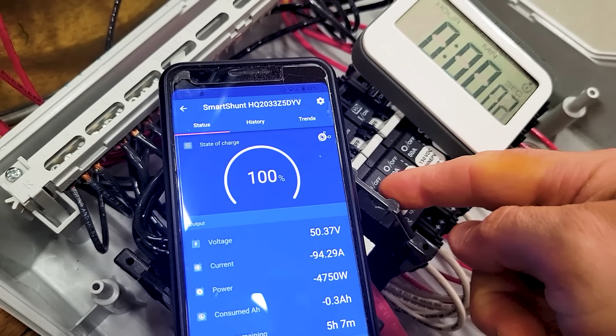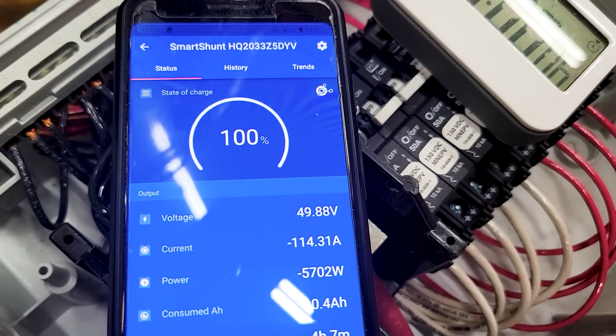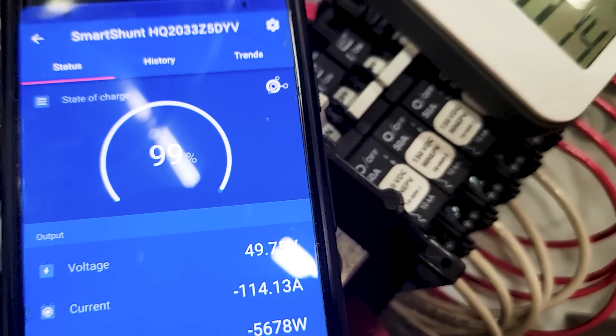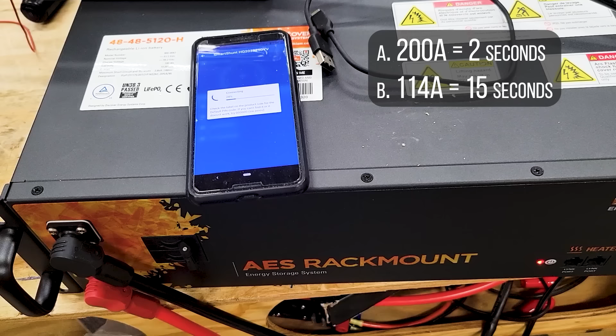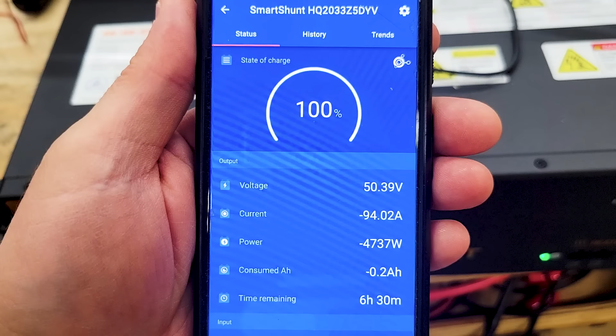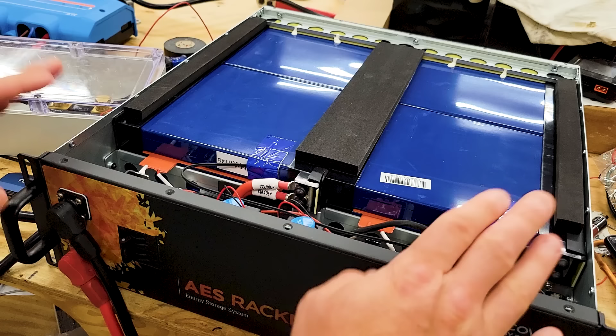Okay, so now we have 95 amps. Let's turn this on. And let's try turning on just one additional circuit breaker. So now we're at 114 amps, and now it died after about 15 seconds. So now we can see we have a red light flashing, the circuit breaker is still on, so now there should be a 2-minute recovery time. Well, good news, the BMS turned itself back on after 2 minutes, and nothing seems to be broken. Okay, everything's looking good. All right, we are ready for the next test.